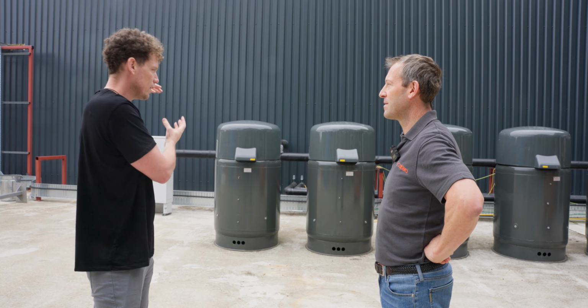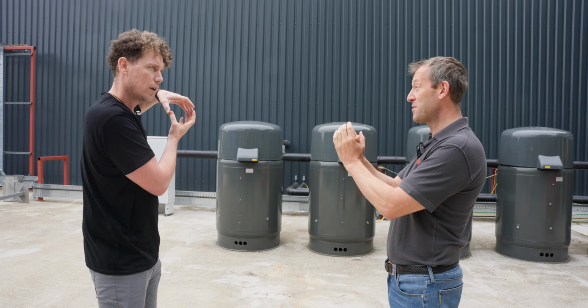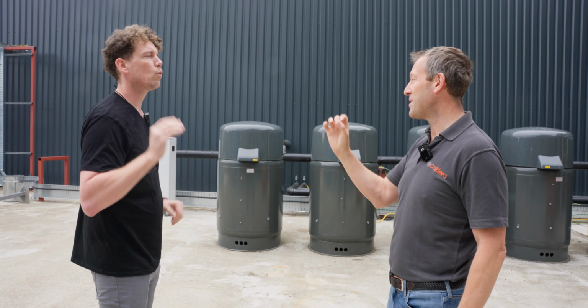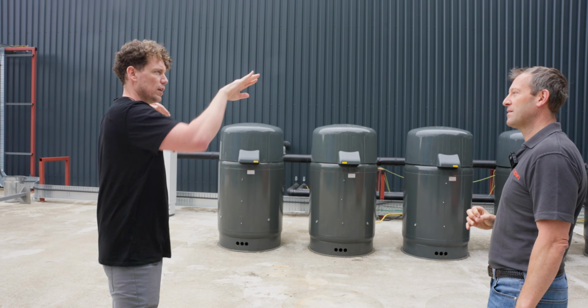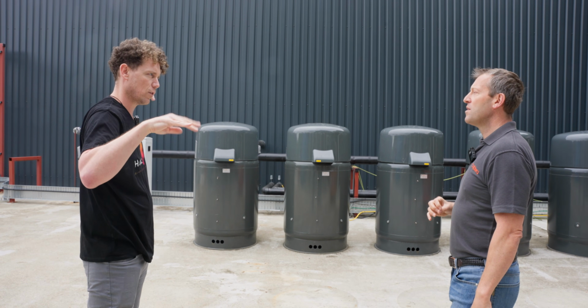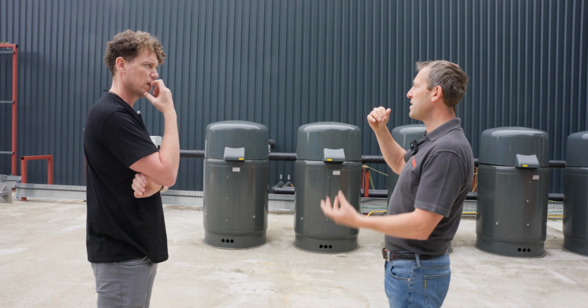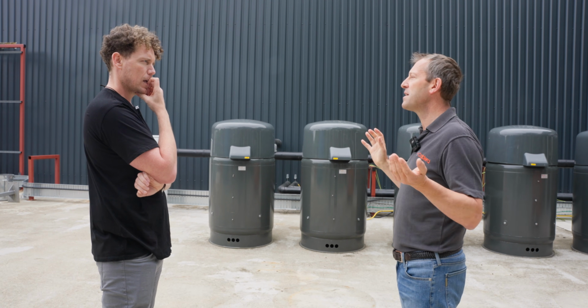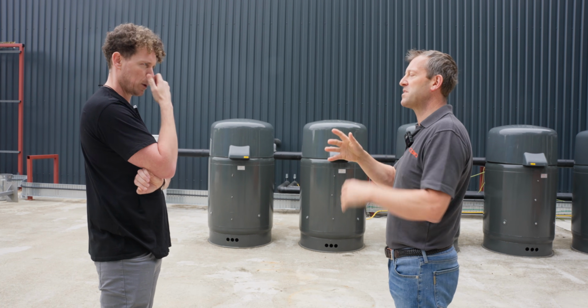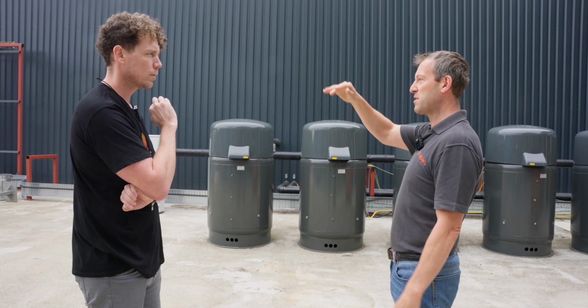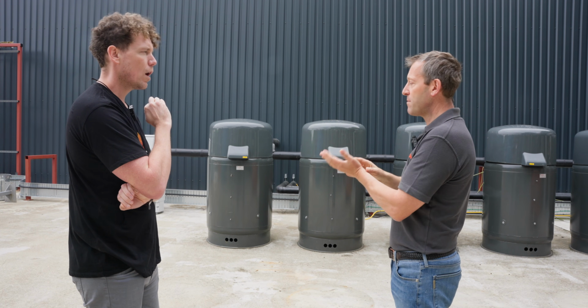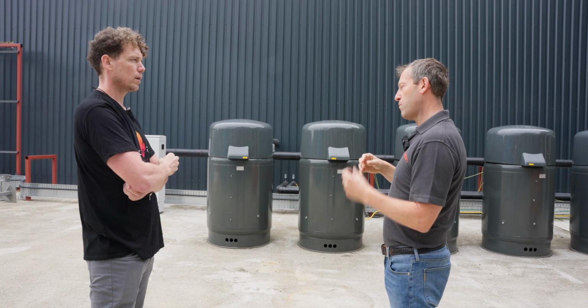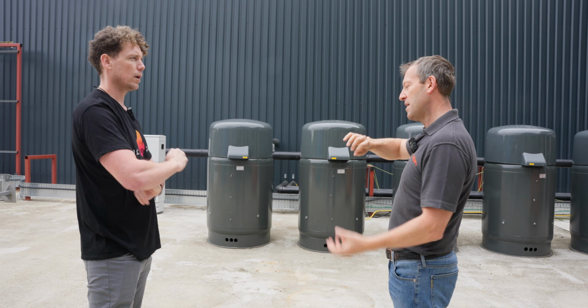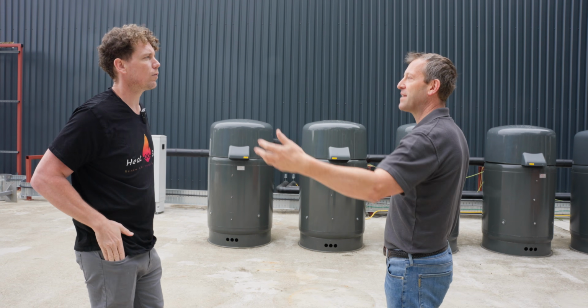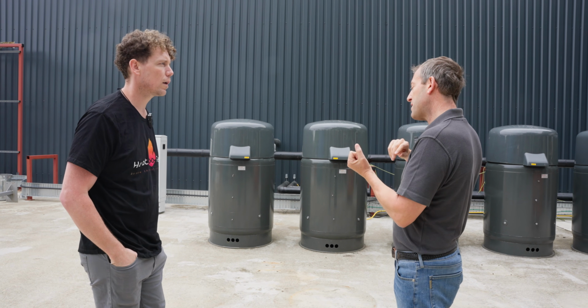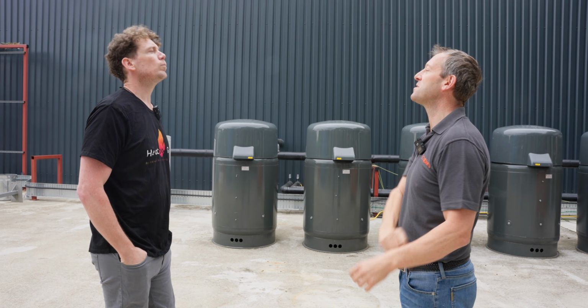Is the return line bigger? No, the water return line is much smaller because it's a condensate line, so it's only the actual liquid. You don't typically use gravity to circulate it. If a circuit is running at, say, 10 bar for easy numbers, that's 183 degrees when it turns from steam back to water. As long as when the water goes back to the boiler house, they drop the pressure at that point, effectively you have pressure in the network that tends to bring the condensate back.